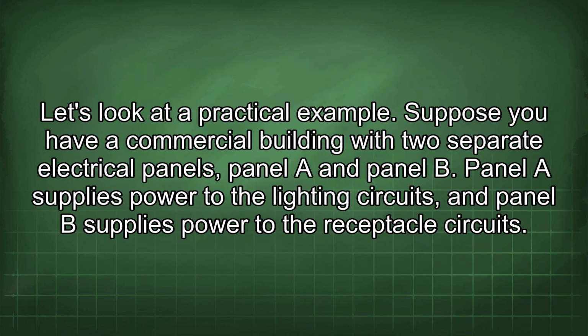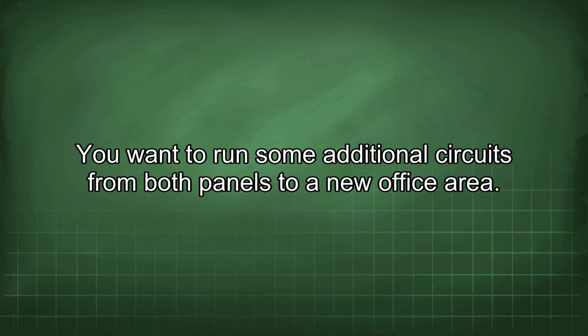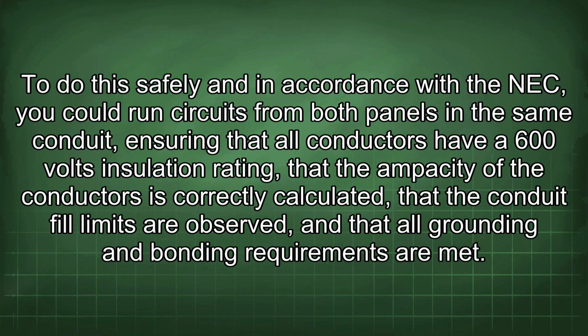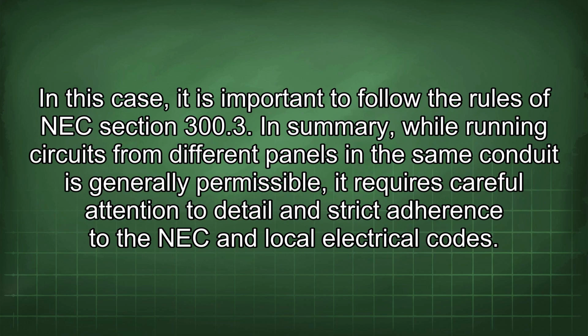Let's look at a practical example. Suppose you have a commercial building with two separate electrical panels, panel A and panel B. Panel A supplies power to the lighting circuits, and panel B supplies power to the receptacle circuits. You want to run some additional circuits from both panels to a new office area. To do this safely and in accordance with the NEC, you could run circuits from both panels in the same conduit, ensuring that all conductors have a 600 volts insulation rating, that the ampacity of the conductors is correctly calculated, that the conduit fill limits are observed, and that all grounding and bonding requirements are met. In this case, it is important to follow the rules of NEC section 300.3.